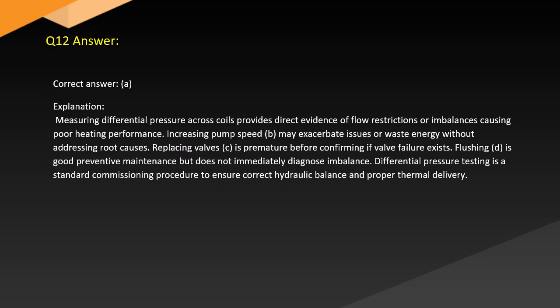Answer. Correct answer. A. Explanation. Measuring differential pressure across coils provides direct evidence of flow restrictions or imbalances causing poor heating performance. Increasing pump speed, B, may exacerbate issues or waste energy without addressing root causes. Replacing valves, C, is premature before confirming if valve failure exists. Flushing, D, is good preventive maintenance but does not immediately diagnose imbalance. Differential pressure testing is standard commissioning procedure to ensure correct hydraulic balance and proper thermal delivery.